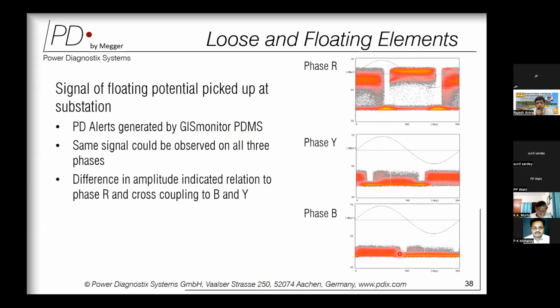So we zero down that there is a little difference in amplitude related to R phase, and cross coupling is happening to B and Y. So now we know that on R phase there is some issue, and B and Y phase are reflecting the issue but to a smaller amplitude, so it's just cross referencing and not a problem. But now on R phase, where exactly is the problem? In a particular sensor, the left side sensor or the right side sensor?